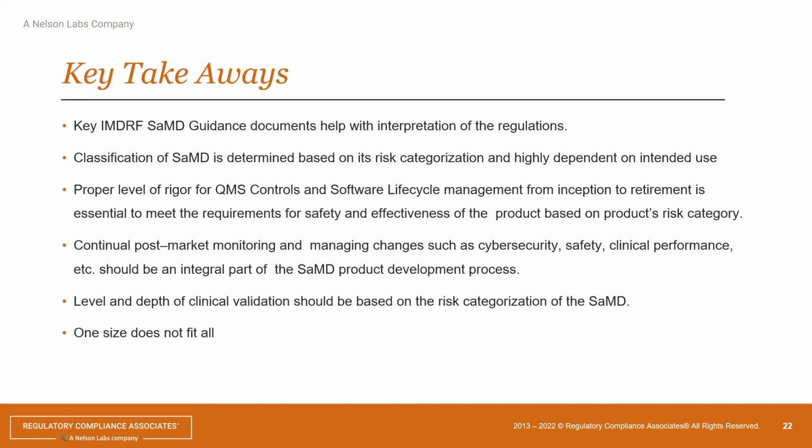Classification of medical devices: not only is it a medical device or not, but if it is, what category is it, is the key, because you really do need to set how much rigor you put into your quality system controls based on the risk level of your product. And as I said before, it's about pre-mitigation risk, not the risk of the device once you've mitigated it.